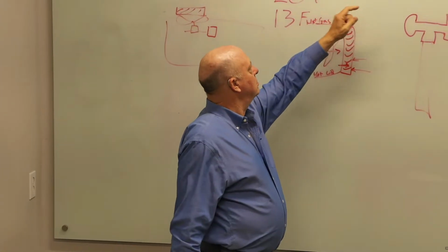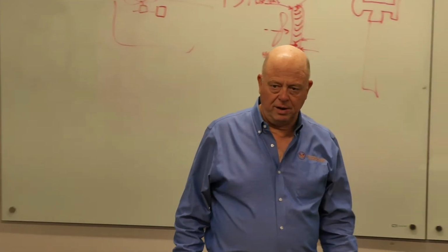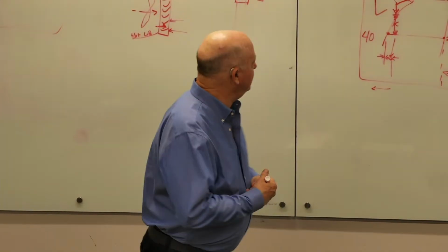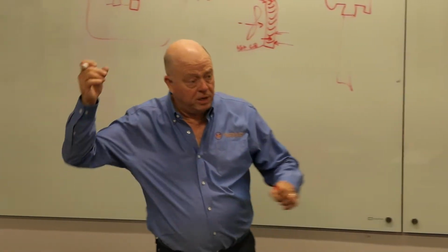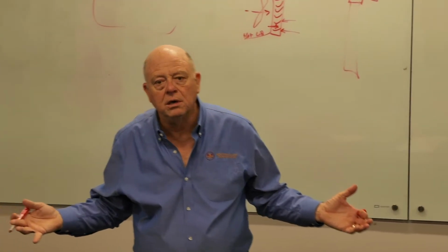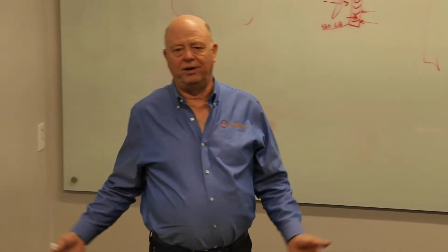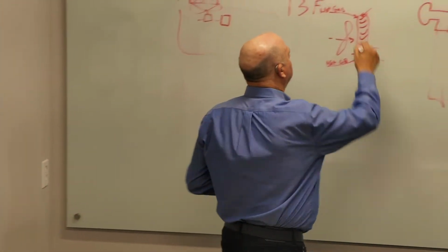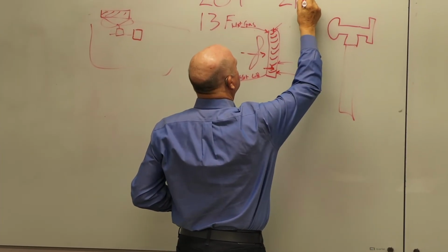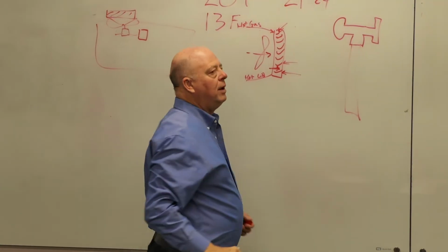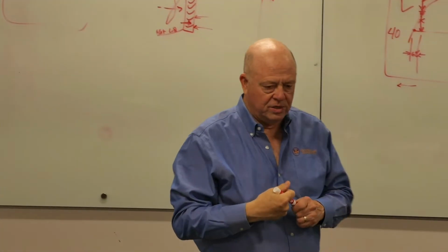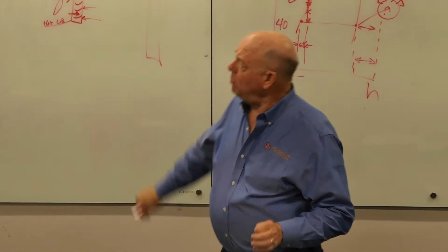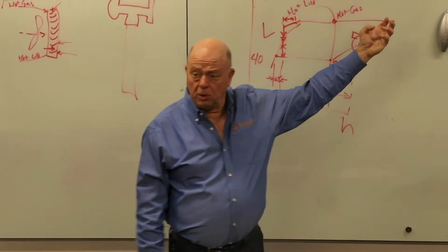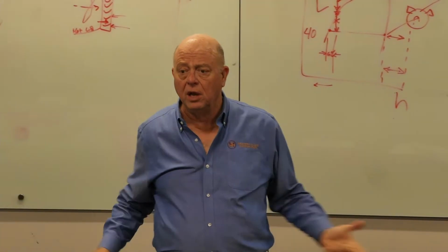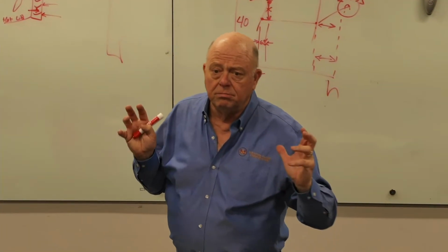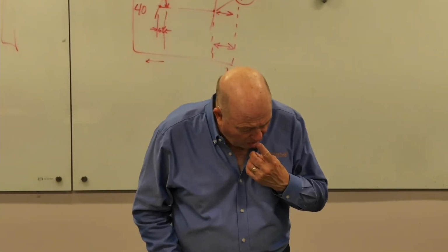This is more like the recommended number. And we ended up deciding for Fox in that situation, through trial and error, to avoid having compressors break, that the right number for us was 21 to 24. That's not what I wrote on the paper, but that's what it was. So that was where we said a little additional superheat. We had the benefit of a 24/7 load, and we didn't break a whole lot more than normal compressors.